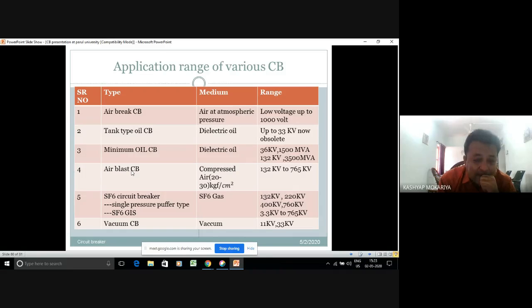So some pneumatic devices are already used there, so in that case it is economical. Airblast circuit breaker also has good arc quenching properties. That's why they are used. You will find mostly SF6 breakers in your substations. Wherever in industry you are working, you will find these SF6 circuit breakers.